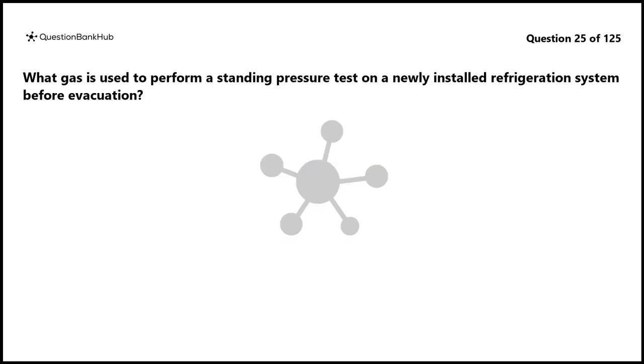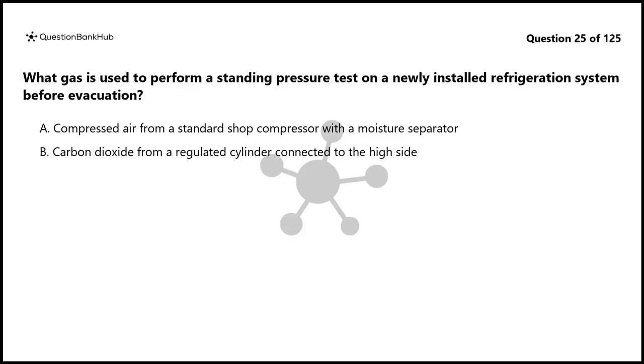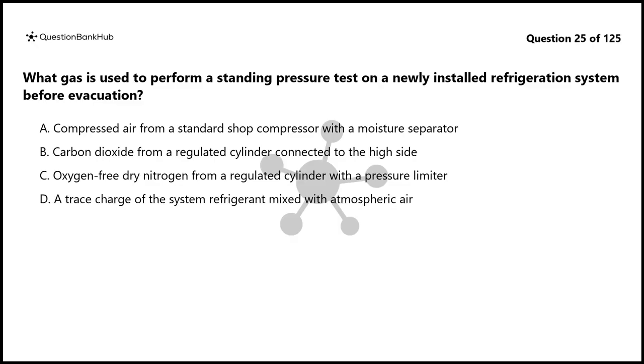Question 25. What gas is used to perform a standing pressure test on a newly installed refrigeration system before evacuation? A. Compressed air from a standard shop compressor with a moisture separator. B. Carbon dioxide from a regulated cylinder connected to the high side. C. Oxygen-free dry nitrogen from a regulated cylinder with a pressure limiter. D. A trace charge of the system refrigerant mixed with atmospheric air.